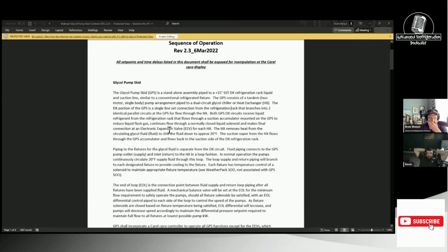No, the rack is fairly stable for how old it is and what it is. That's going to affect it, right? Well, yeah, but you can't just slap a brand new skid on a 20-year-old rack and expect it to be perfect with no capacity control. It is what it is. There are no unloaders on the rack at all. There are 2 compressors with unloaders. At the time, they were running constant. Pretty much every compressor was running. I got you. And the head's plenty high because of the condenser.